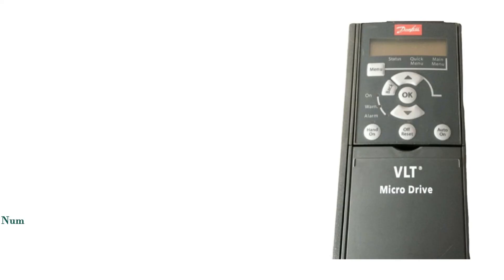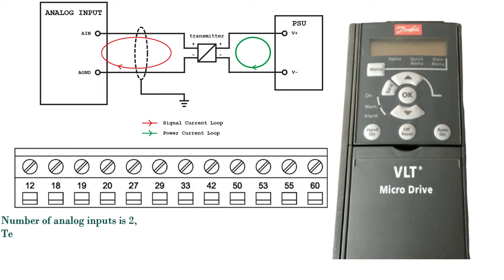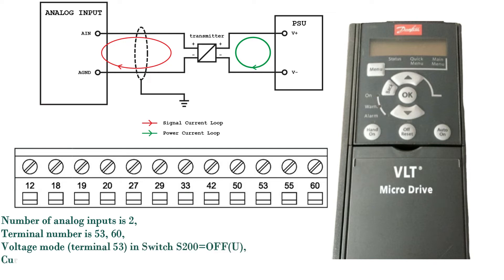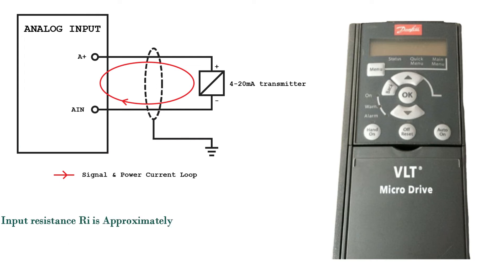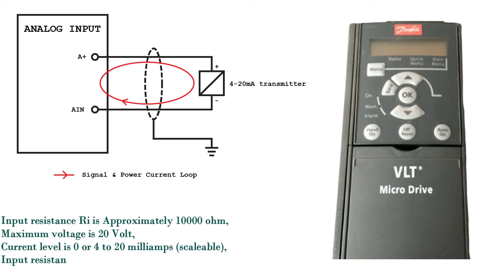Analog inputs: number of analog inputs is 2; terminal numbers are 53 and 60. Voltage mode: terminal 53, switch S200 = OFF (U). Current mode: terminals 53 and 60, switch S200 = ON (I). Voltage level is 0 to 10 volt; input resistance RIN approximately 10,000 ohm; maximum voltage is 20 volt. Current level is 0 or 4 to 20 milliamps, scalable; input resistance RIN approximately 200 ohm; maximum current is 30 milliamps.